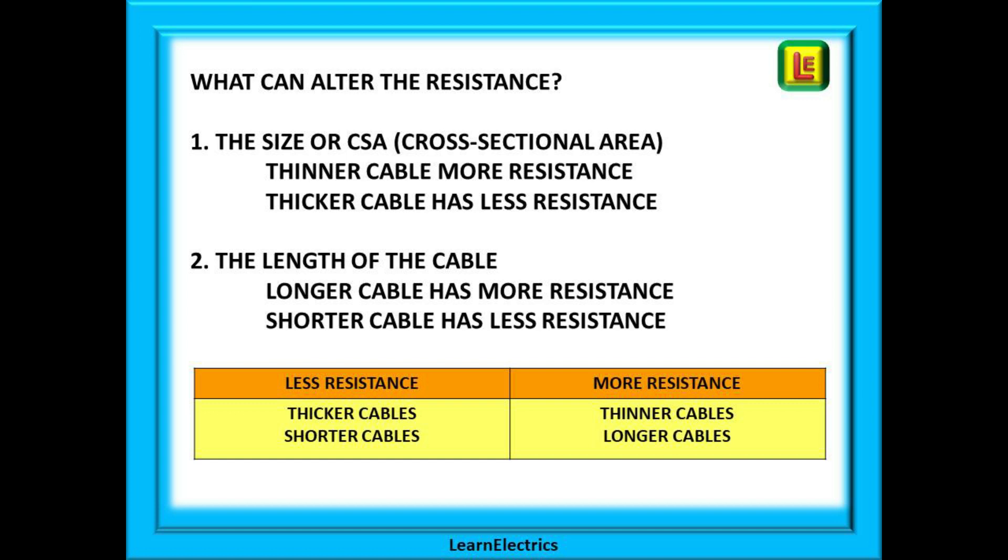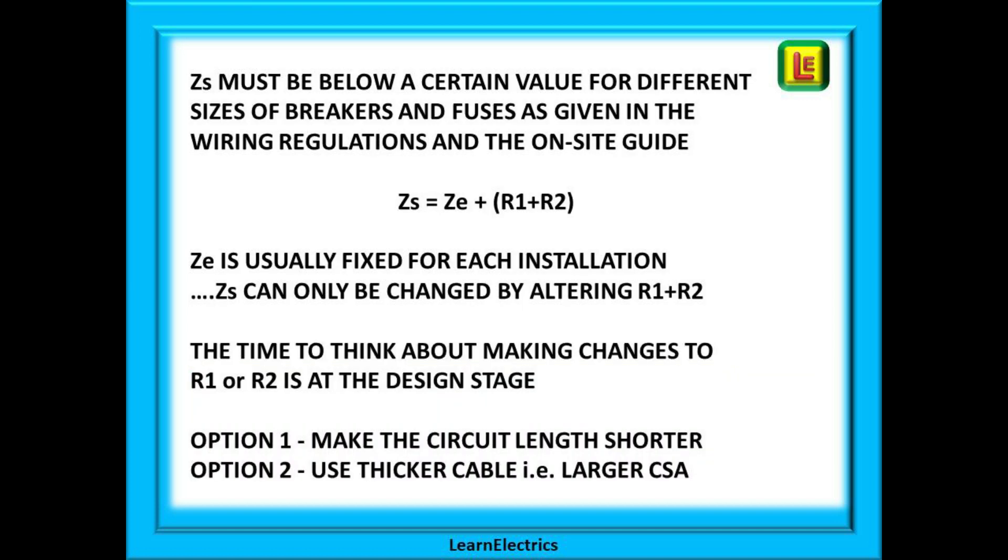The best solution is to have thick cables on short runs, but we also have to take into account the cost of the copper cable itself. Copper is not cheap, so we need to have the cable size big enough to carry the expected fault current without overheating the cables, but not so big that we are paying for extra copper that we do not need. This is why there are tables giving maximum values of ZS which includes R1 plus R2. ZS must be below a certain value for different sizes of breakers and fuses, and these are given in the wiring regulations and the on-site guide.